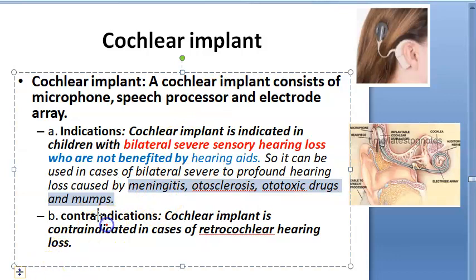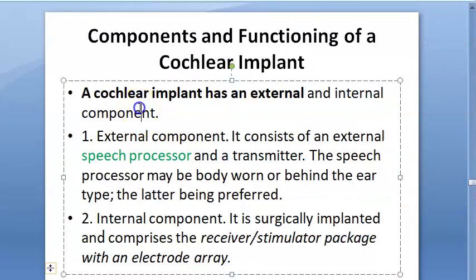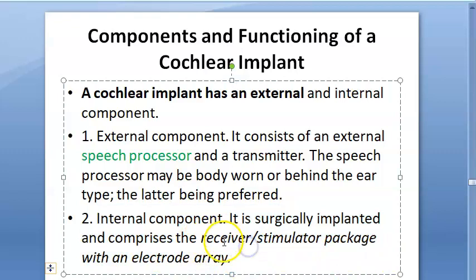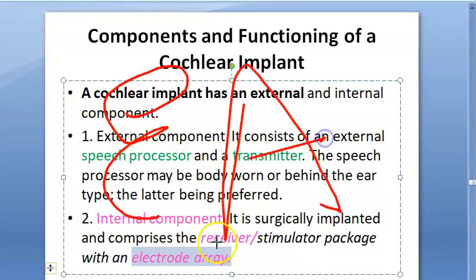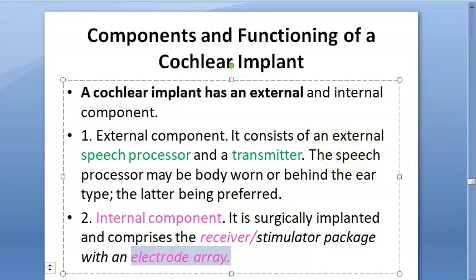Contraindication: it is contraindicated if there is retro-cochlear hearing loss - behind the cochlea. If the hearing loss is behind the cochlea, a cochlear implant cannot fix it; that may be a nerve issue. In retro-cochlear hearing loss you cannot give this. Components: external component is the speech processor; internal component includes receiver, electrode array. The most important element of a cochlear implant is the electrode array - everything else externally is almost the same as other hearing devices.